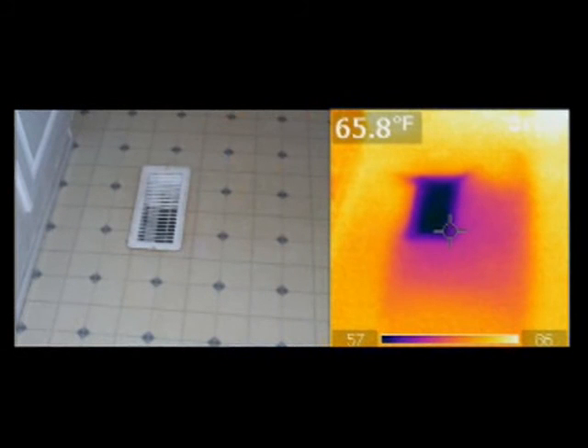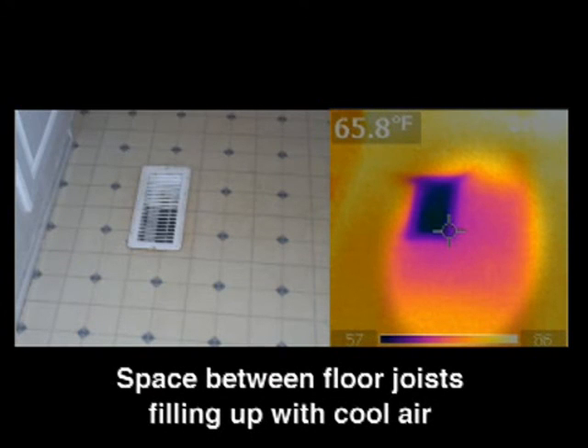Look at the next set of photos. This is a mobile home, and air is leaking into the joist area, the blank spot in the floor between the joists. It's not visible to the eyes, but the cold air going into this area underneath the floor was creating a battle between hot and cold air in the crawl space underneath the mobile home. This too is conducive to a moisture condition, which you don't want while living in a mobile home - moisture collecting underneath the floor and coming in through the ductwork because hot and cold air are battling each other in the floor area.